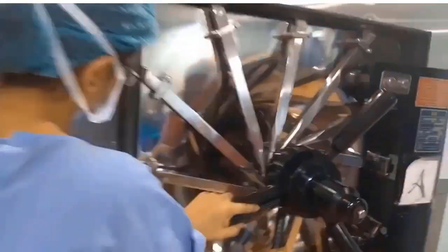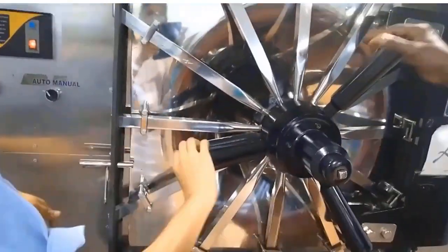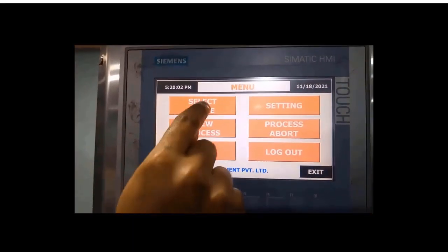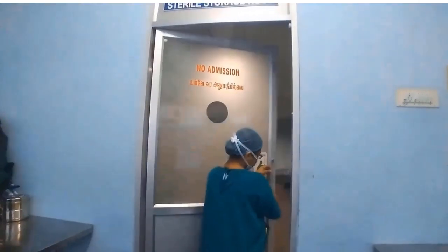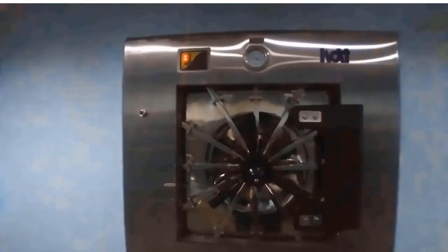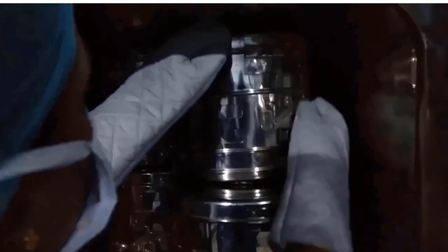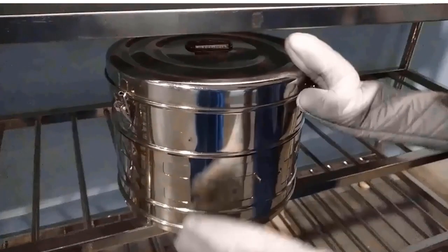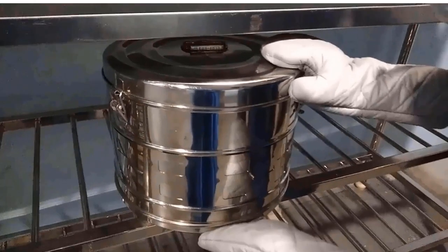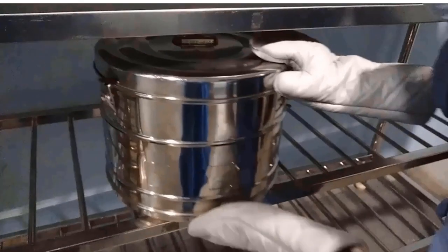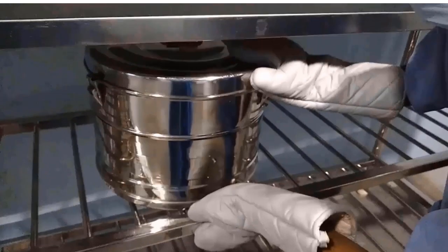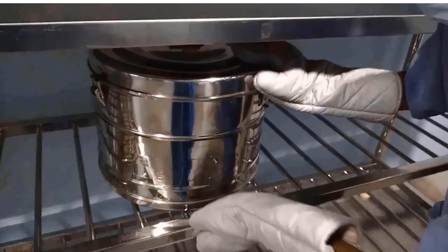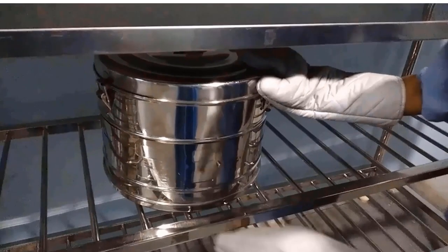Monitor the process of the autoclave after the things are unloaded in the sterile storage area. When the door is open, check the color change of indicators. Close the bin holes immediately before keeping in the sterile storage area. The sterile storage area should not be damp or wet, with limited access of persons to avoid growth of bacteria or fungi. UV lights or AC should be kept inside.